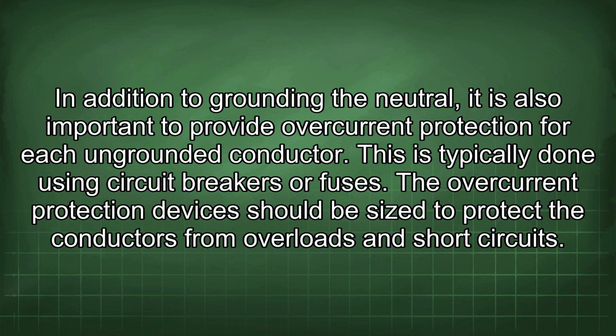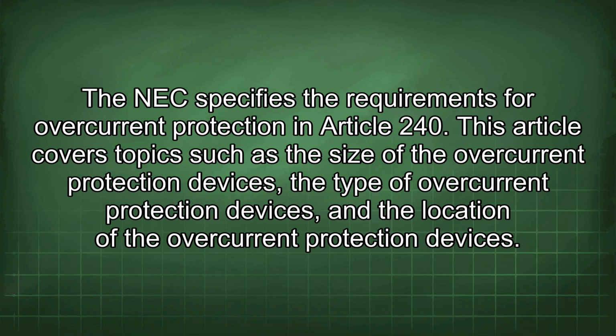In addition to grounding the neutral, it is also important to provide overcurrent protection for each ungrounded conductor. This is typically done using circuit breakers or fuses. The overcurrent protection devices should be sized to protect the conductors from overloads and short circuits. The NEC specifies the requirements for overcurrent protection in Article 240.